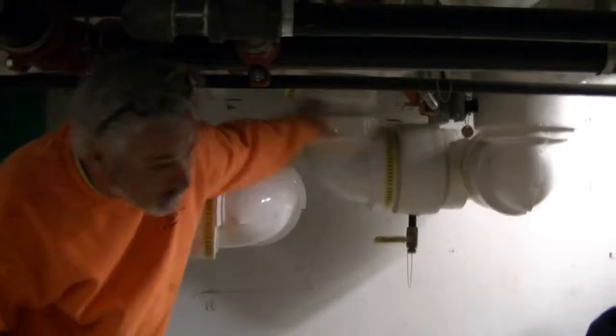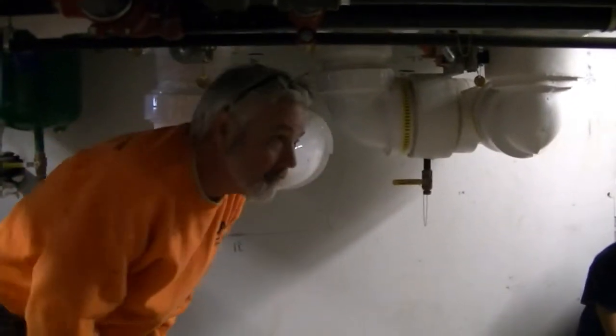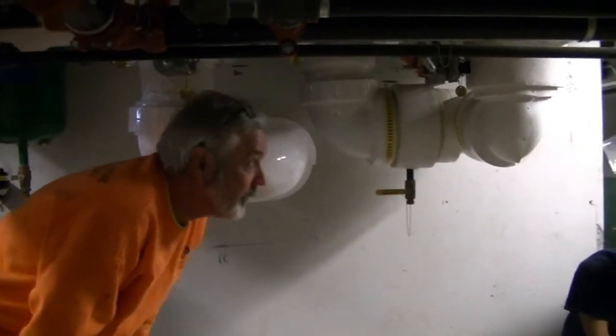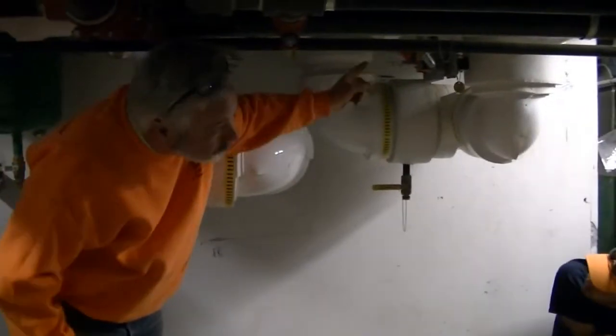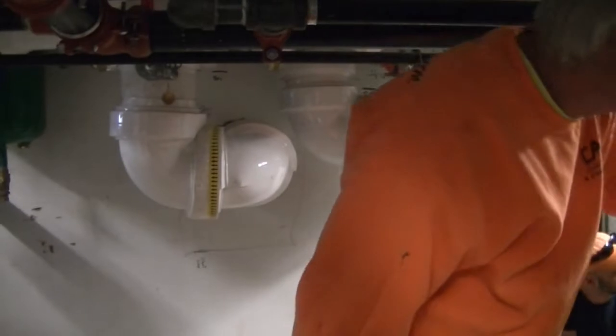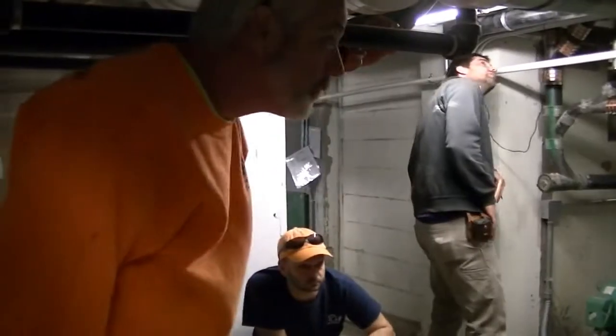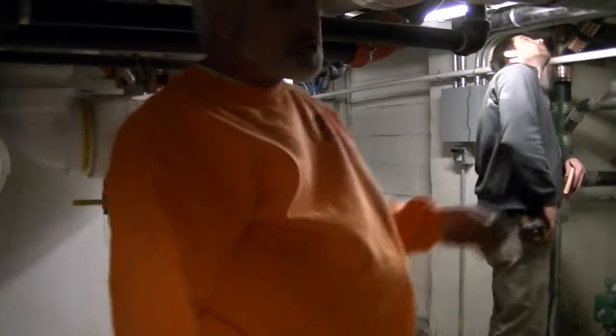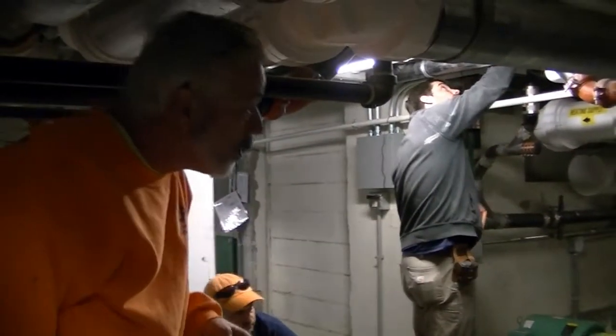Kevin mentioned that to you earlier. And this valve will modulate to whatever you set that reset graph to. Alright? Once the water mixes through here, it travels out, comes down here, goes into your main building heating pumps, and heads out towards the system. Alright? Now I just showed you guys the domestic hot water pumps. Okay? I'm going to head over here.